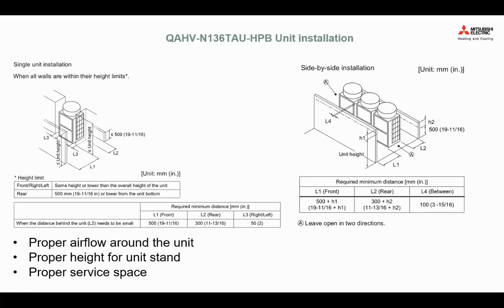And lastly, the proper service space, as I mentioned before. Everything you see here in the installation manual is really the minimum requirement for the unit to perform properly. But you also have to think about the people who are actually installing and servicing the unit, maybe leaving a few inches extra so they can reach in and have proper space to install and service the unit, or at least clean the coil.